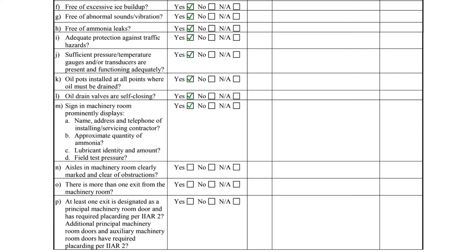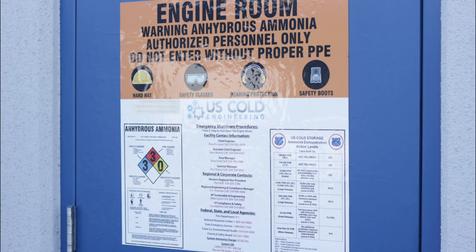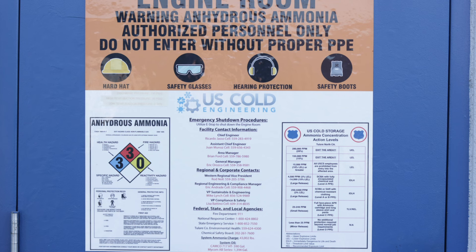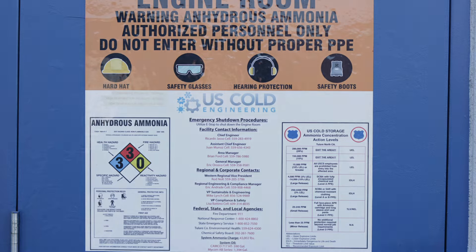Item M asks if a sign in the machinery room prominently displays the name, address, and telephone number of the installing servicing contractor. The sign must also include the approximate quantity of ammonia in the system, lubricant name and amount, and the field test pressure applied when the system was constructed.